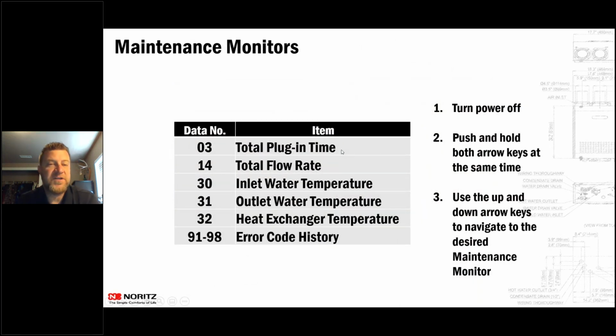Every manufacturer has maintenance monitors that are built into their controllers. So with ours, you can press the up and down arrow keys and hold them, and then you'll hear a beep, and it'll flash 03. Once you get to 03, you can press the up and down arrows to get to different maintenance monitors. If we're ever called with an issue, or our tech support's ever called with an issue, they always walk everybody through these certain maintenance monitors to make sure that everything in there is correct.